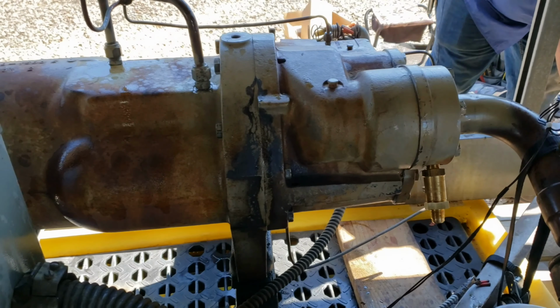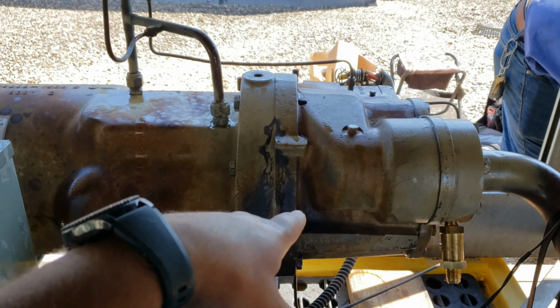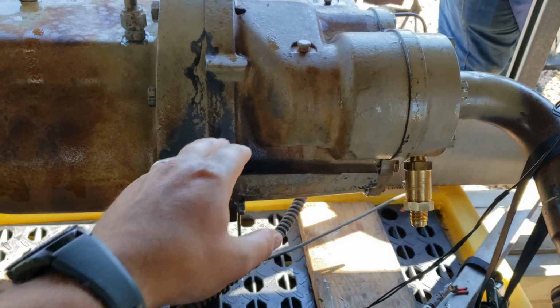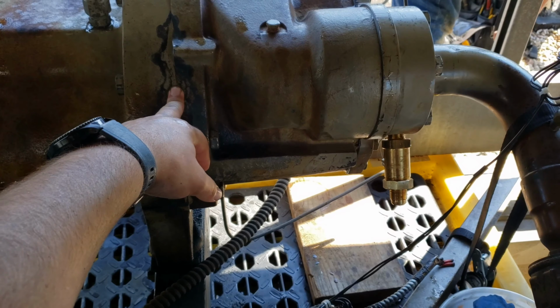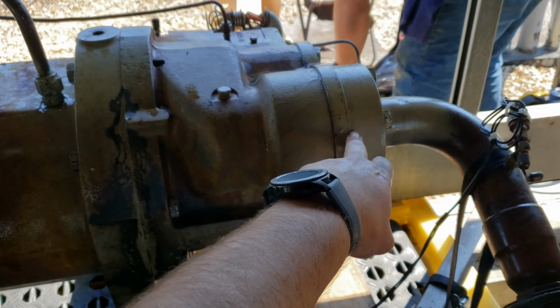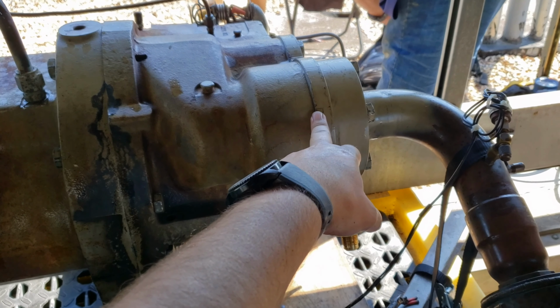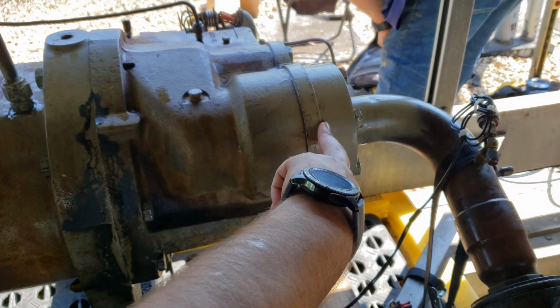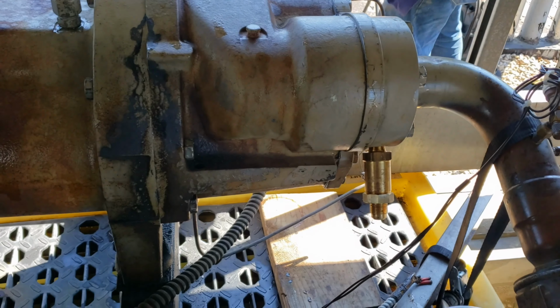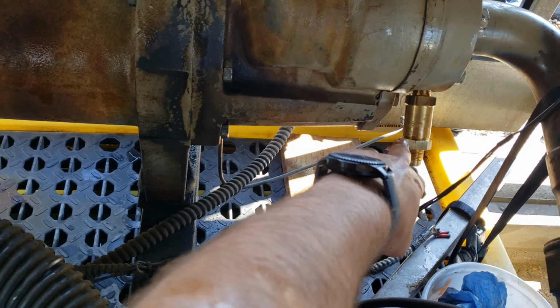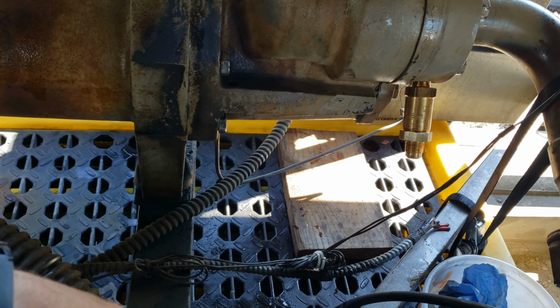So that's a wrap, guys. We got the whole discharge assembly done. In the end, we replaced this O-ring in here, replaced this gasket on this front plate, and replaced the discharge O-ring all together. We also replaced the relief valve. It was leaking.